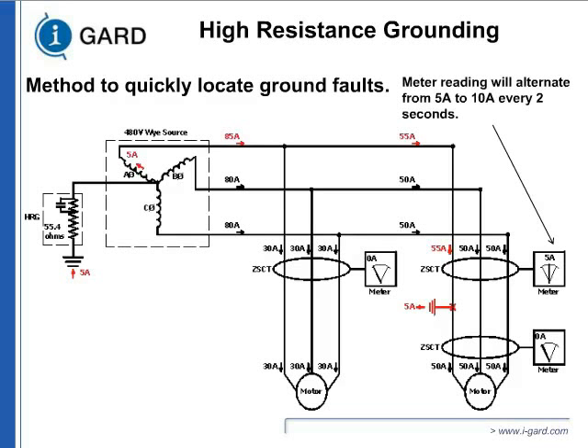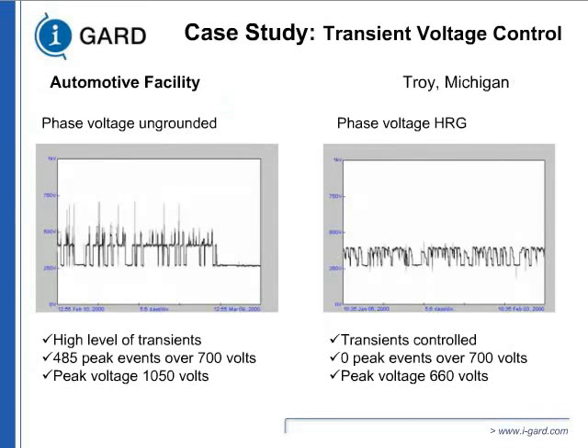Now, the same study that you saw, now see the difference. After they installed the high resistance grounding, before they were 485 peak events over 700 volts. Okay. After high resistance grounding, they were 0 over 700 volts. Peak voltage 660 volts is because of the pulsing when it goes on, it records as an intermittent fault. That's the reason peak voltage was 660 volts. If it didn't have to pulse, it would not have any over voltage at all. Okay?